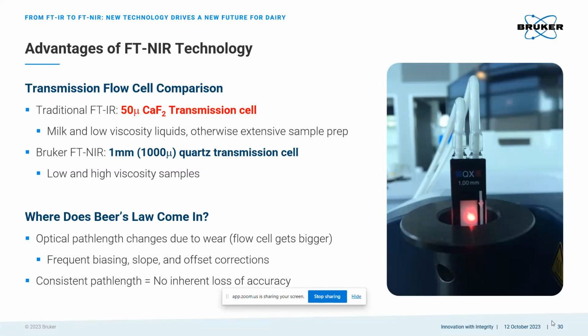And as that calcium fluoride cell deteriorates over time, frequent bias, slope, and offset adjustments are required to maintain accuracy of the measurement. And it's also why these cells need to be changed out frequently. So between monitoring for biases and making calibration adjustments due to cell wear and inevitably replacing these cells on a frequent basis, that's a lot of effort to account for a variable that is avoidable with an NIR quartz flow cell. These quartz flow cells have a long lifetime and no regular exchange is required so long as proper cleaning procedures are applied. And since that path length D, going back to our equation, is going to remain the same, we'll experience no inherent loss of accuracy over time when we use these quartz flow cells.